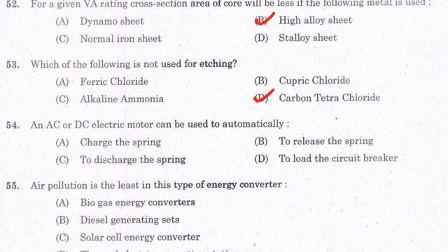An AC or DC electric motor can be used to automatically charge the spring, to release the spring, to discharge the spring, to load the circuit breaker. Right answer is option A, charge the spring.